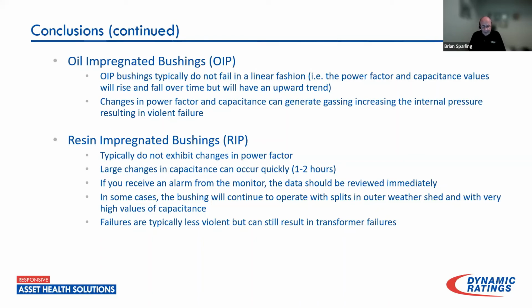When it comes to RIP bushings, given how extreme the failure rate is, the principle has changed, the practice has changed, the response has changed. Now when that alarm comes in and it is an RIP bushing and they see that rate of change, the call is made immediately to operations to take that transformer out of service. Then they go and double check and follow up the day after, or when convenient, to confirm, and then go up for the bushing replacement. So it has resulted in a change in practice depending on the type of construction of the bushing, OIP or RIP. It made necessary changes to the alarm response to alarms from bushing monitors.